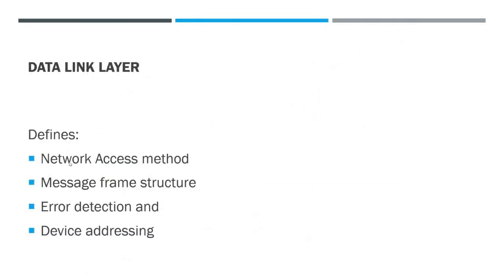Within the data link layer, we define the network access method — we'll talk about different ones like master-slave, polling, and burst, which change as we go between protocols. There's also message frame structure — the size of the frame, how many data bits, error bits, stop bits, start bits, that kind of thing, defining how the data is packaged. Error detection and device addressing are also contained within the data link layer — this is all internal stuff.